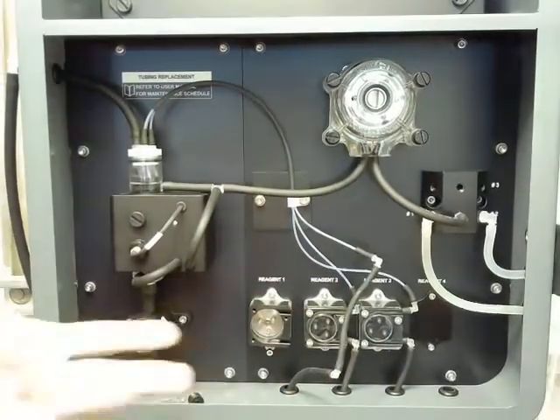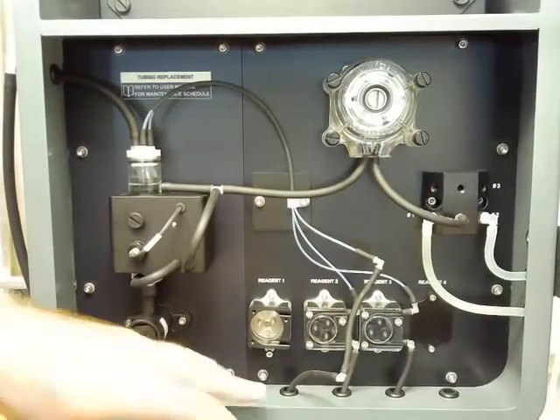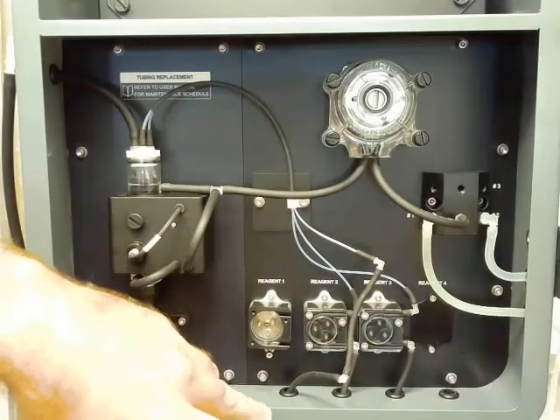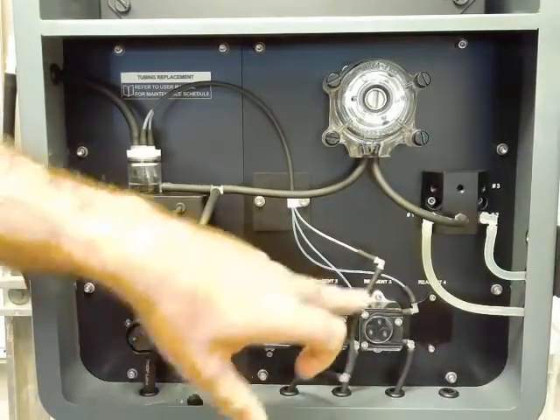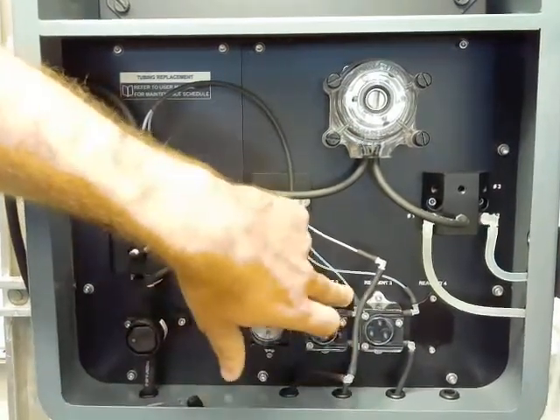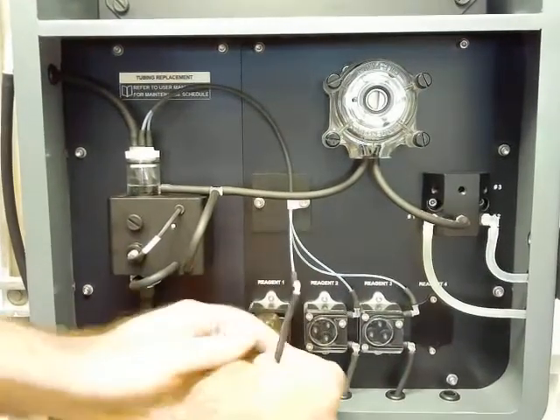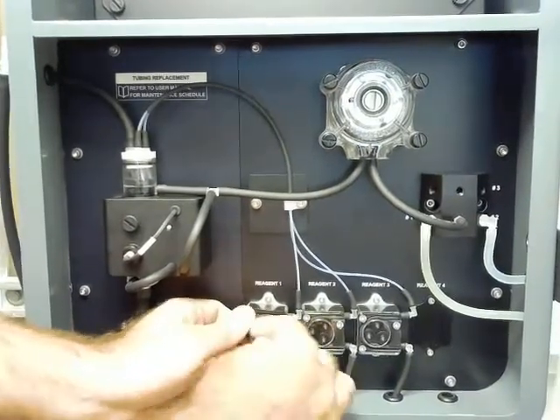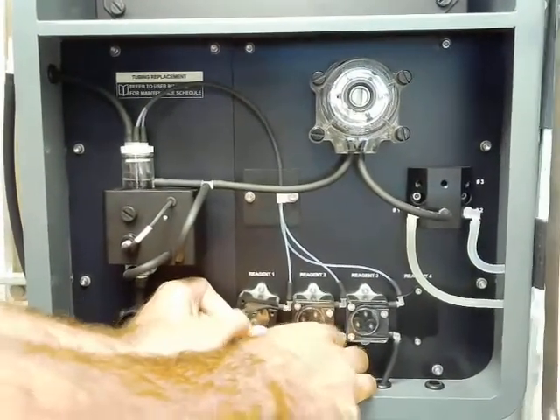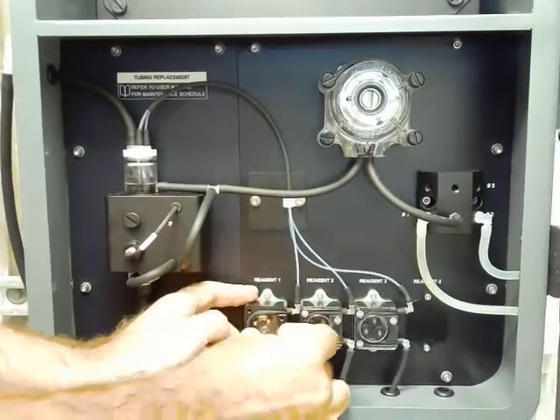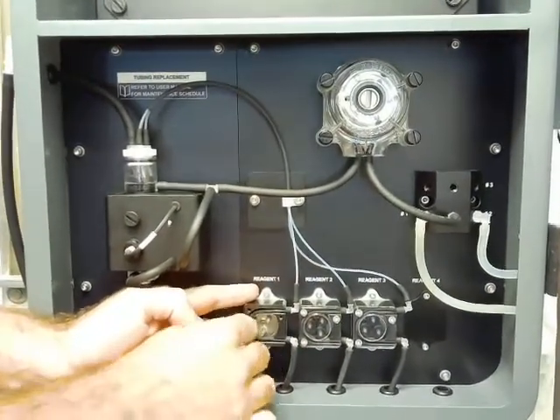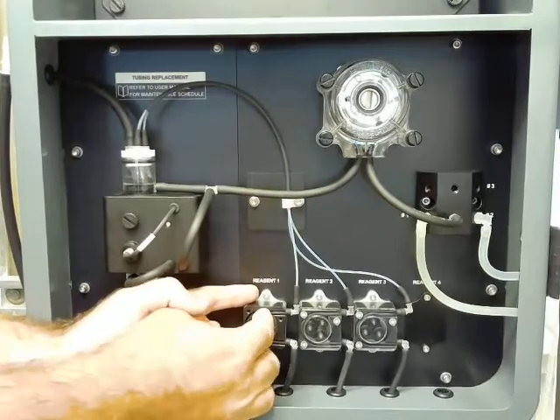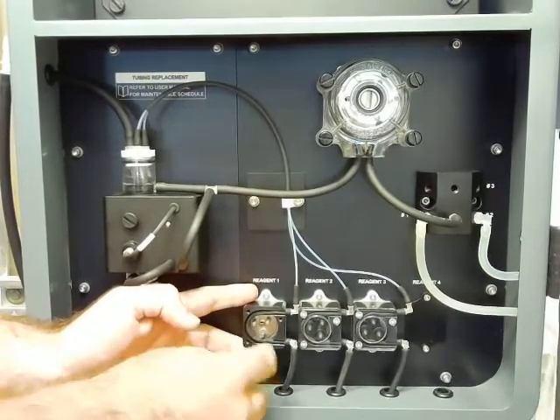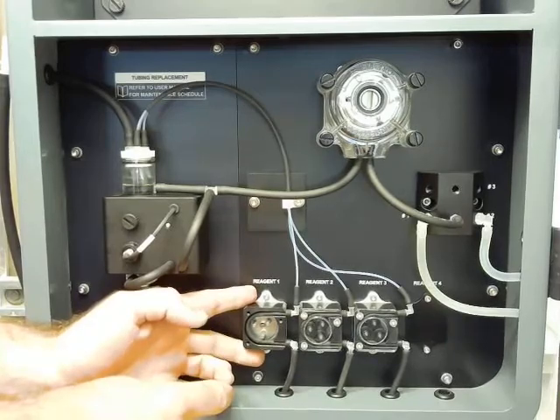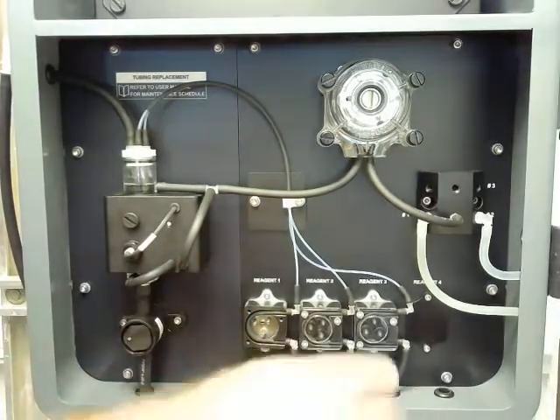So I like to connect the new tubing first, and then put the tubing into the pump head, as opposed to connecting the tubes afterwards, because my fingers don't really fit between these valves, or the pumps rather. So once we have it connected, slide it through the openings in the pump head. And again, we'll just make sure that it's in and the curve of the tube matches the pump head. We don't want too much slack inside or it be too tight, put a little bit too much resistance on the pump motor.